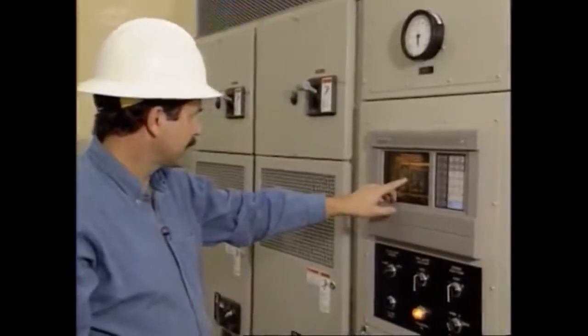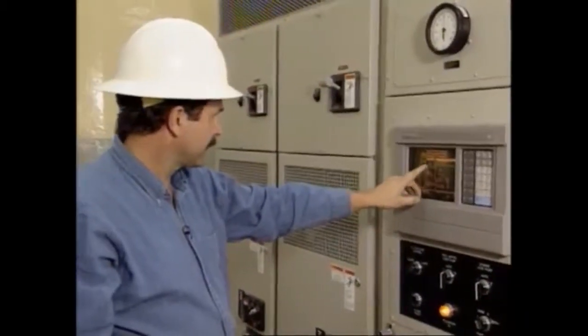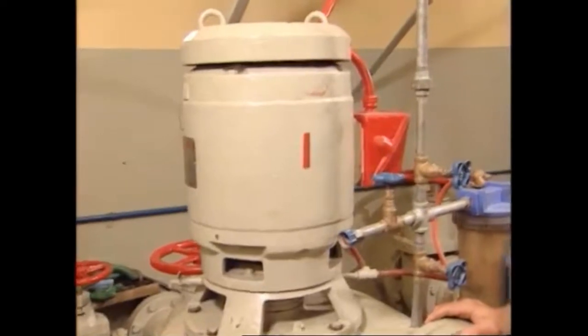You need to find the source of overloading. Is the head or capacity requirement higher than that designed? If so, increase the horsepower. Always remember, improper changes can have disastrous effects on the motor, so know what you're doing. And if in doubt, consult the manual on equipment protective devices.